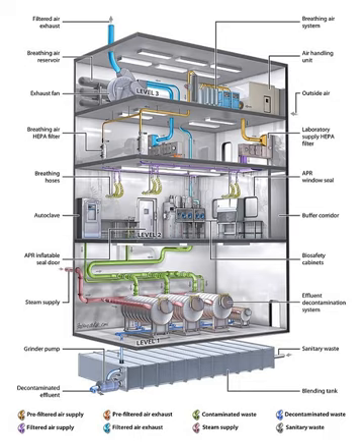All procedures involving infectious material must be done within a biological safety cabinet. Laboratory personnel must wear solid front protective clothing, i.e. gowns that tie in the back. This cannot be worn outside of the laboratory and must be discarded or decontaminated after each use. A laboratory-specific biosafety manual must be drafted which details how the laboratory will operate in compliance with all safety requirements. In addition, the facility which houses the BSL-3 laboratory must have certain features to ensure appropriate containment. The entrance to the laboratory must be separated from areas of the building with unrestricted traffic flow.